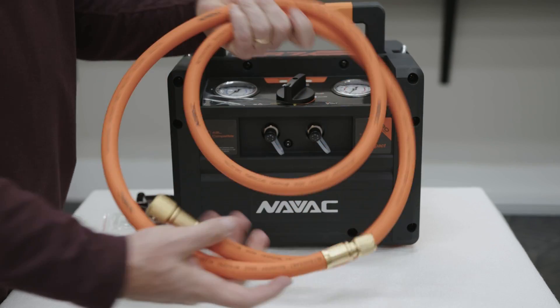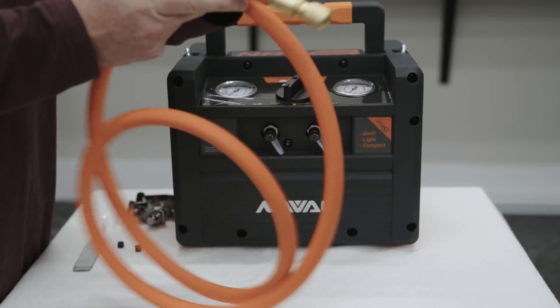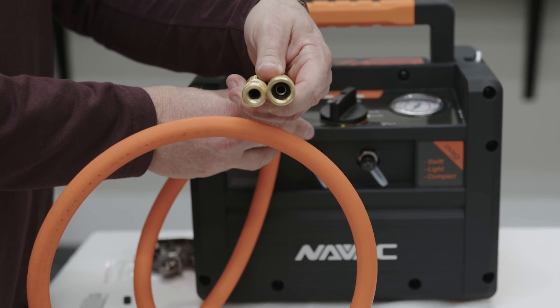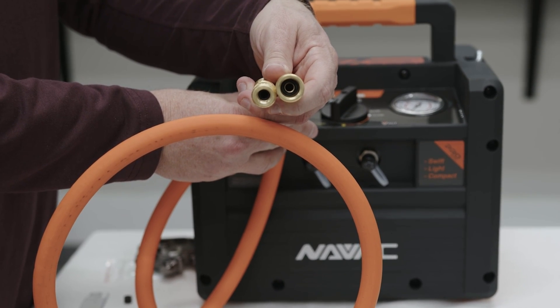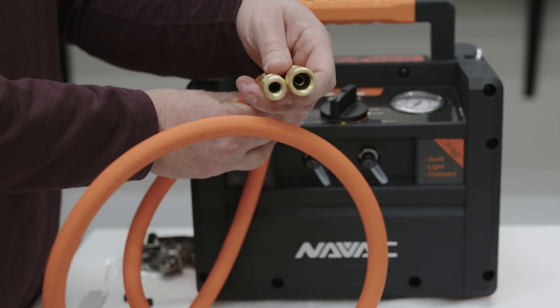Keep in mind, because this is an evacuation and recovery hose and not a charging hose, you're not going to have core depressors on either side. These are designed to be used on ports that have no core depressor only — otherwise there will be no flow through the hose.